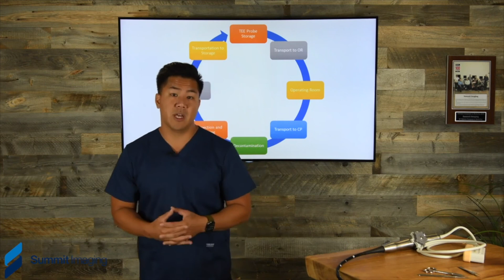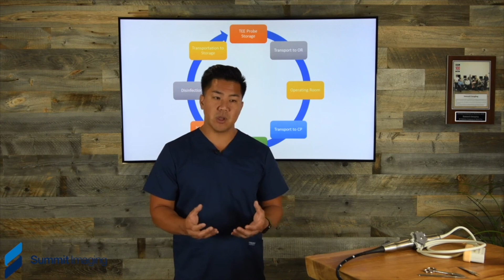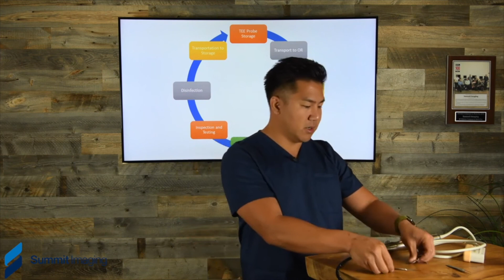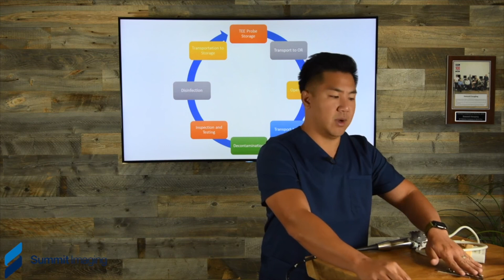All right, now let's talk about the next phase, which is in the operating room. We've actually joined a lot of procedures just to observe how the equipment's being used, but more importantly, what's being used around it environmentally that could be inducing failures on TEE probes and other standard probes as well. But let's just talk about TEE probes. And we have some surgical tools here. We have a scalpel, scissors, other types of things that are all extraordinarily sharp. And one thing is, when the technicians are prepping for a procedure, we've seen these sharp tools right next to the transducer on the table.